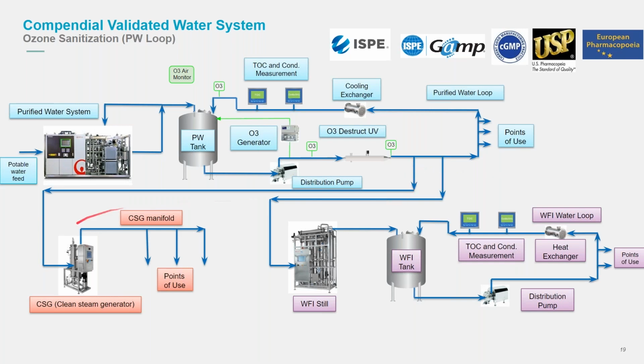Typically from that loop, you may have an application for clean steam. So the purified water feeds a clean steam generator. Again, you're changing the phase from water to steam, and that steam is used in things like autoclaves or washers that may be required on a manufacturing site.